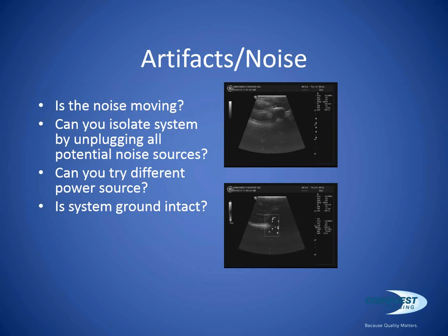And what about the facility ground? I was sharing with the clinical engineering department at the site today a unique problem I had years ago, where a system was manifesting noise and we replaced everything on the system and could not get the noise to go away. The solution, and this is a true story, was actually finding the building ground and taking a garden hose and trickling water on that ground overnight to have it better conduct noise to ground. So the facility ground can actually be a problem.